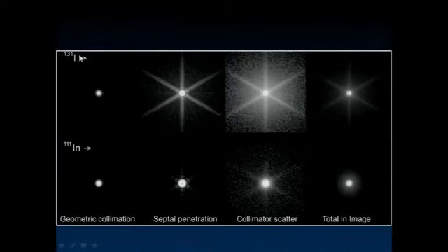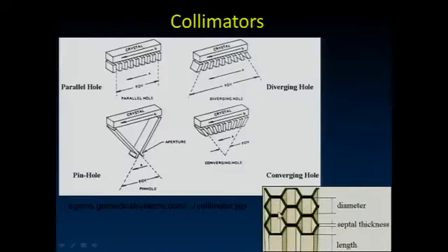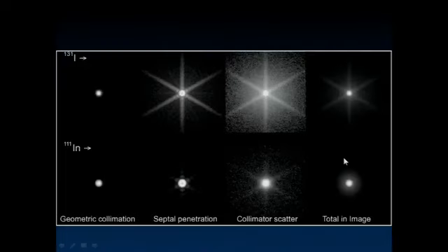Here's I-131, which, yes, is a beta emitter, but also decays through the production of some high-energy gamma rays, and they will frankly pass right through the thin lead septa of some collimators. And so you get this septal artifact, where gamma rays are passing through the walls of some of these septa, and that star pattern corresponds to the orientation of the walls in that collimator. You'll see that here. Okay.